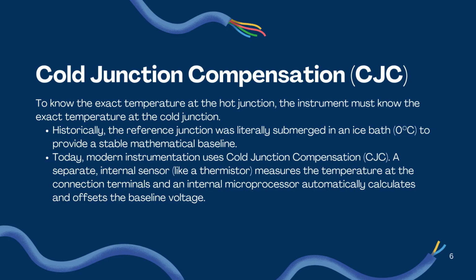Now it's about the cold junction compensation, CJC. To know the exact temperature at the hot junction, the instrument must know the exact temperature at the cold junction. Historically, the reference junction was literally submerged in an ice bath at 0 degrees Celsius to provide a stable mathematical baseline. Today, modern instrumentation uses cold junction compensation, CJC. A separate internal sensor like a thermistor measures the temperature at the connection terminals, and an internal microprocessor automatically calculates and offsets the baseline voltage.